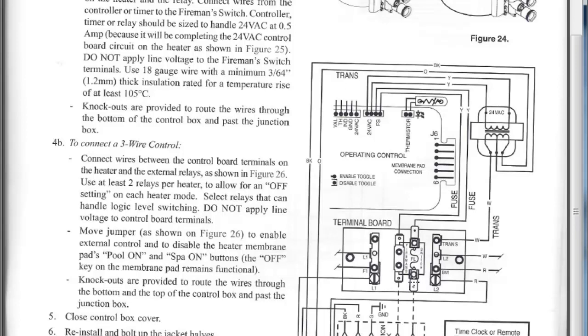And tells this controller to turn the switch off at 104 degrees. Now, the only reason I tell you not to put wire nuts and to leave that little yellow wire there is for testing. It makes testing easier. If you know your water is flowing and your heater is not running, you can do this quickly without meters. But if you don't know water is properly going through your heater, don't do this test.